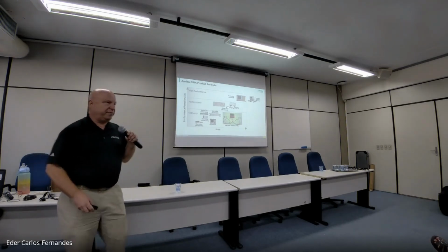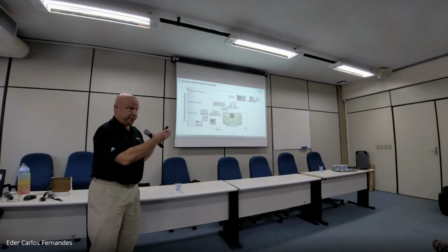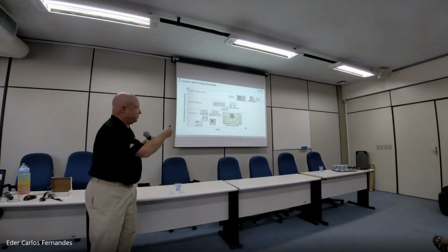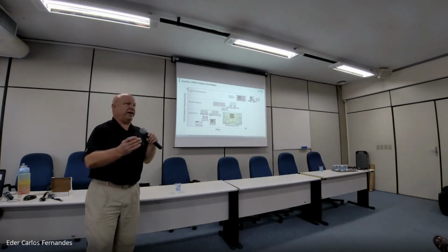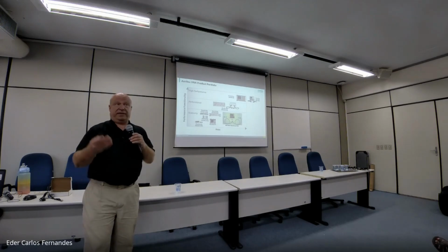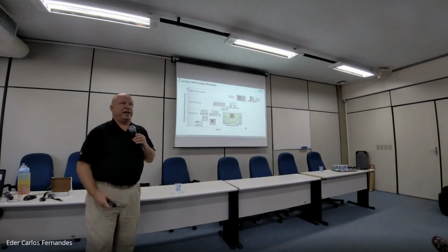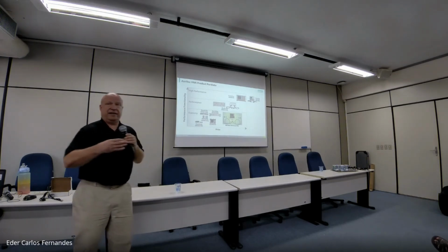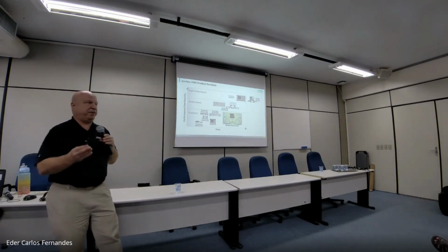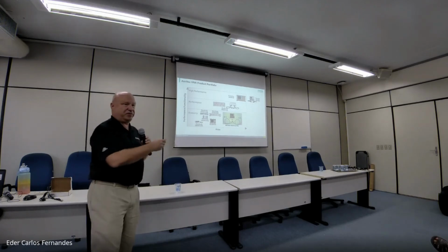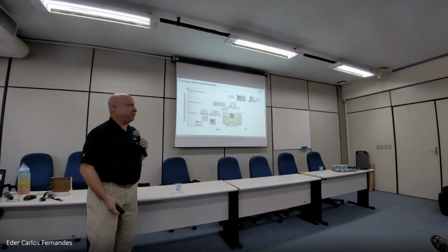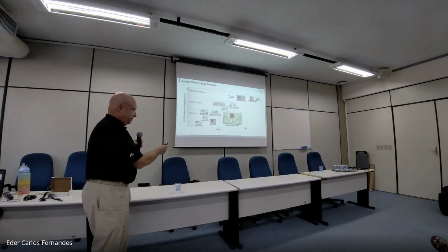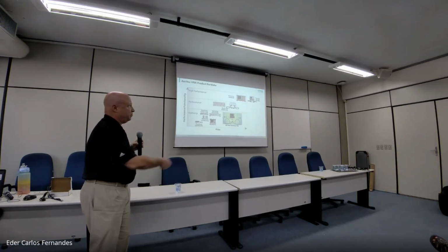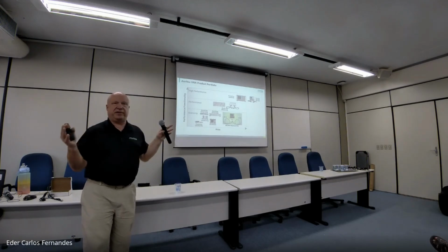We can do the same measurements as we do with a benchtop 2-port VNA, do it in a distributed way. Where would that application be? In a chamber, perhaps. In an aircraft. In a ship. Someplace where the cable that you want to measure cannot be moved. So you need to bring the instrument to the cable that you want to test. Well, if you take the benchtop VNA out there, you have to attach long cables to get to where your cable is that you want to measure.